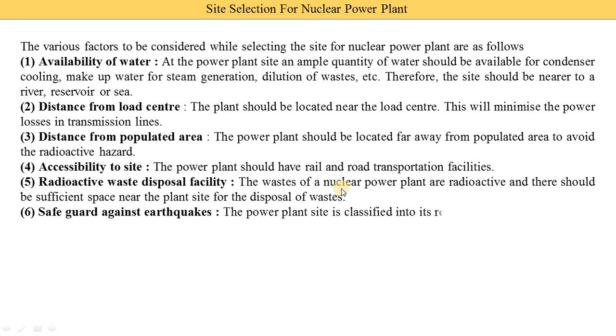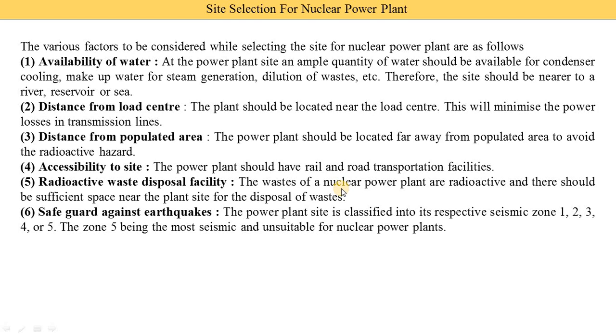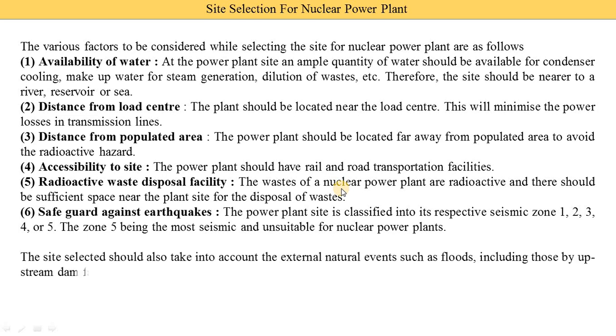The last point is safeguard against earthquakes. The power plant site is classified into its respective seismic zone — zone one, zone two, zone three, zone four, or zone five. Zone five is the most seismic and is unsuitable for nuclear plants. If any place falls in seismic zone five, we are not able to install a nuclear power plant there. The site selected shall also take into account external natural events such as floods, upstream dam failures, and tropical cyclones.